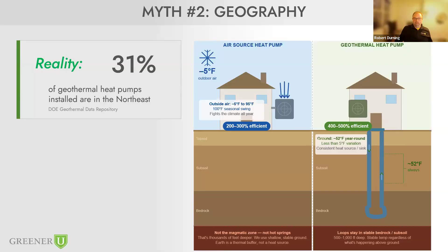The benefit of using the ground as your medium to reject heat or pull heat from is that it's very stable year round. So generally speaking, you're talking about 45 to 55 degrees year round when you get below the frost line. We're not going as far down to get towards that magmatic zone, but we're trying to use the ground as a very stable medium to heat that, and we can do that very well here in New England.